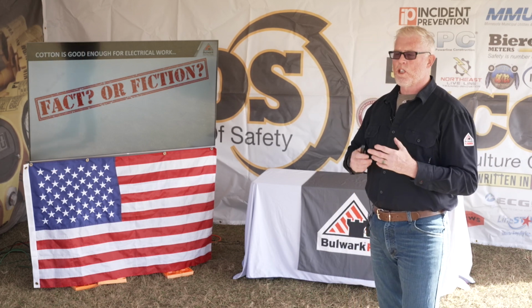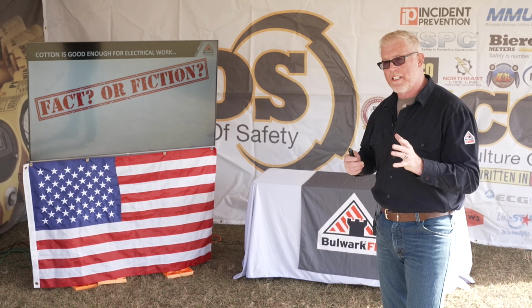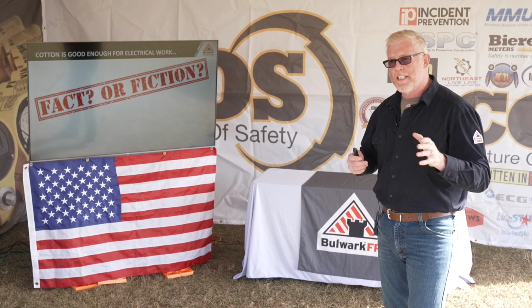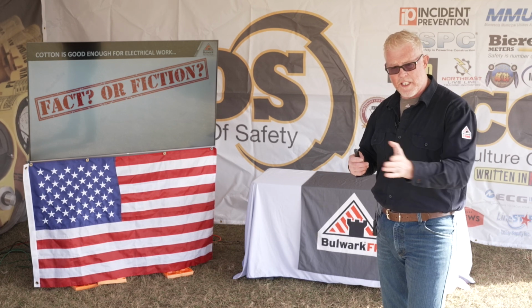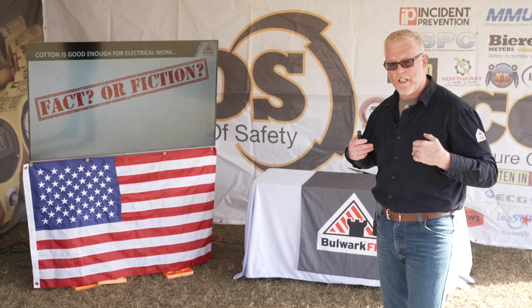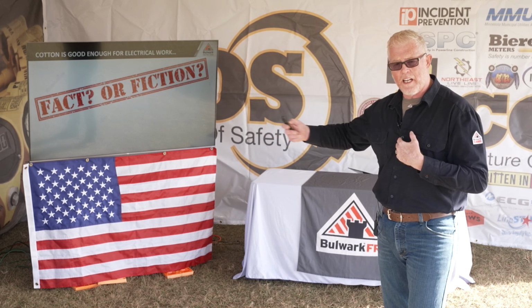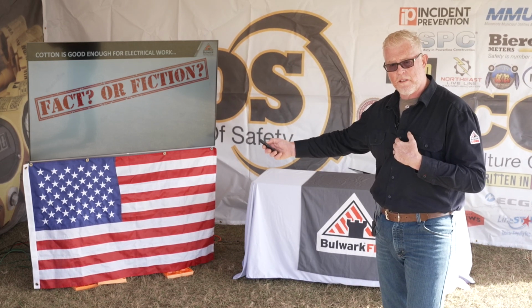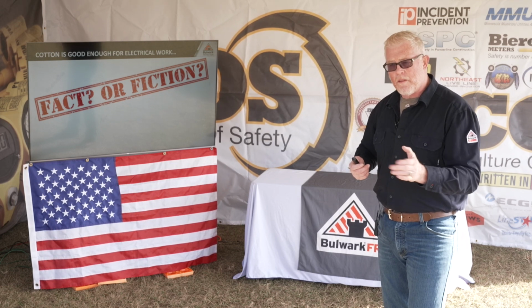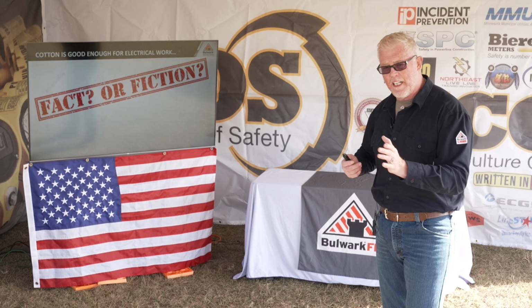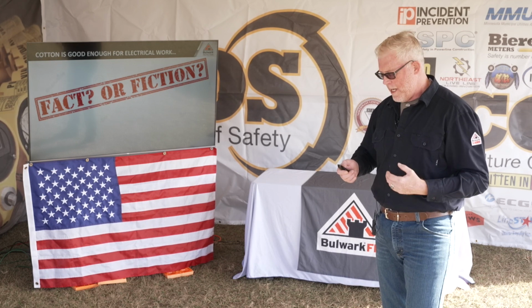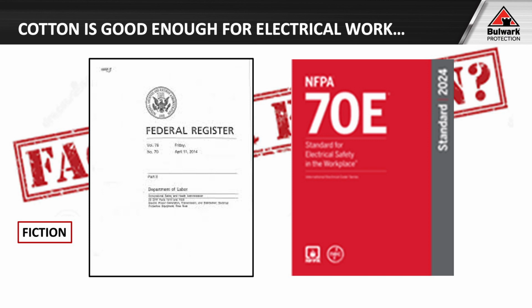Lastly, thankfully this was probably about a decade ago now, 1910-269 changed, and in 2014 we stated that you need flame-resistant arc-rated clothing reasonable to an estimation of the incident energy you're exposed to. Prior to that, cotton was acceptable. We still see some lingering belief that cotton's good enough for electrical work. Thankfully that's worked its way out, but the reason we don't want to do this is the law says you can't, and on the general industry side, the nationally recognized consensus standard NFPA 70E says you can't. So why can't you?